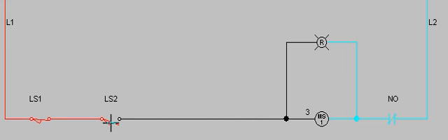When we activate limit switch 2, then now we have current flow through the coil of motor starter 1, and again I went ahead and added a pilot light to make it easier to see that it's on. So this particular circuit is in series. If either one of these drops out, we have no current flow. It interrupts the flow.